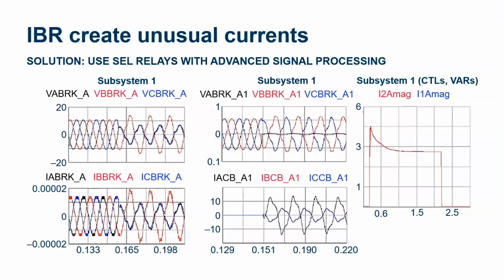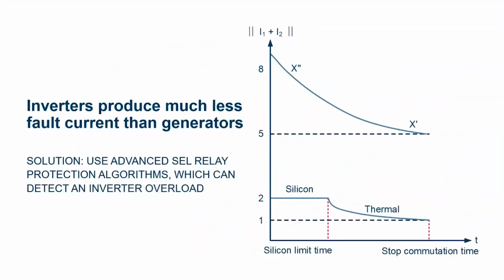When you decode those problems, you need a device like an SEL relay that has advanced signal processing to decode. Are those Clarke's components correct? Are those Park's components correct? Are the sequence components correct? Is this truly what the inverter is doing? And let me now take this data and go talk to said inverter manufacturer. Please now correct your firmware. This happens daily for us.